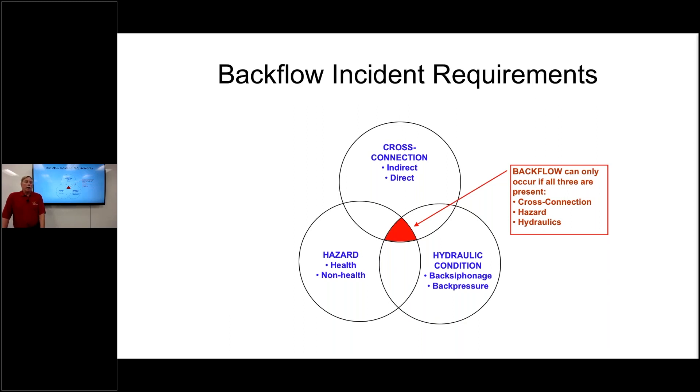We needed to have the hazard. And not only that, we also needed to have the hydraulic condition, something to actually move that hazardous material into the drinking water system. So as indicated in this Venn diagram, that red area in the middle is where those three issues coincide. And it only is at that point that we truly get a backflow incident that occurs. This is where we find many times people don't understand that the three parts of this Venn diagram have to happen concurrently for a backflow incident.